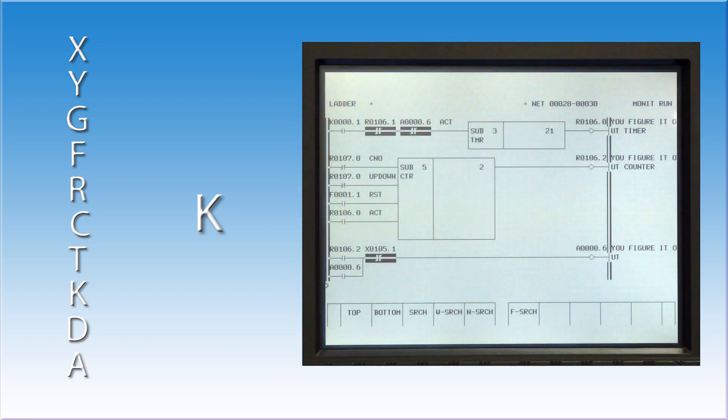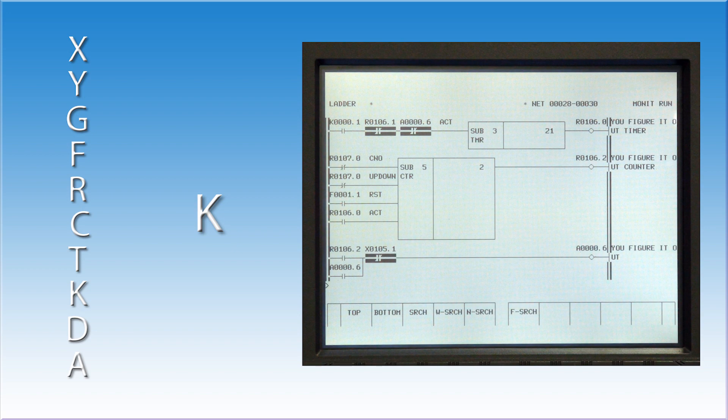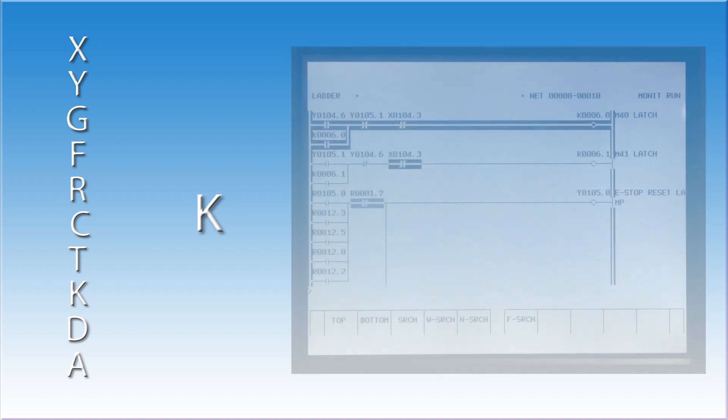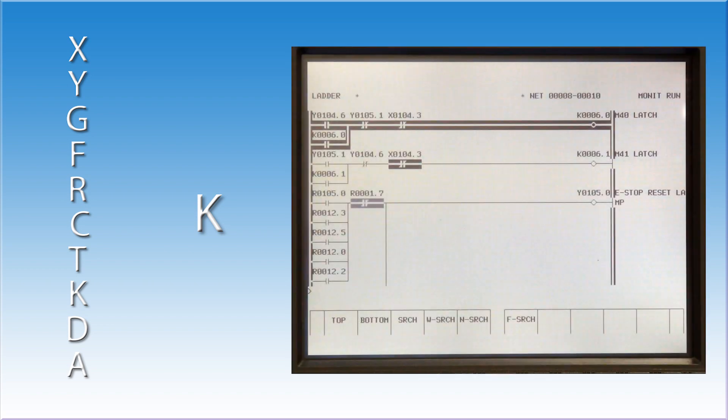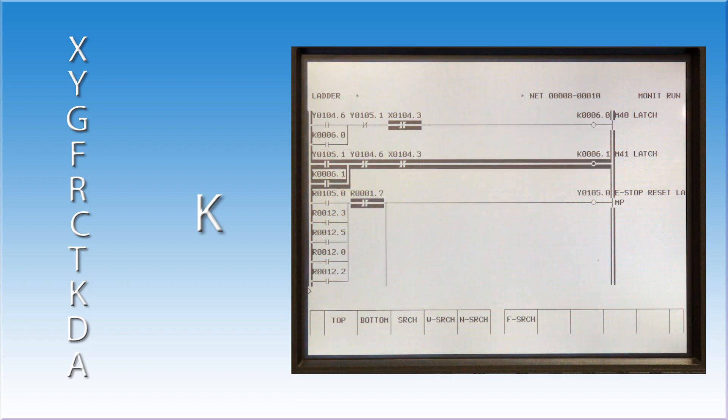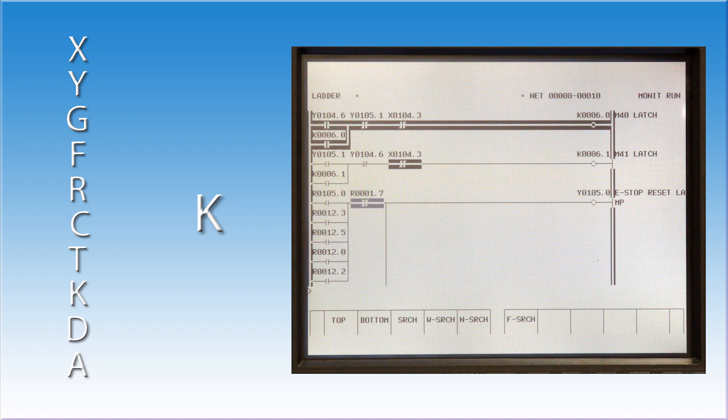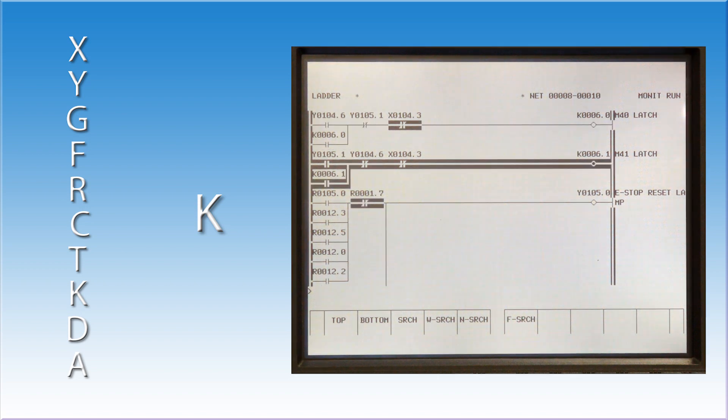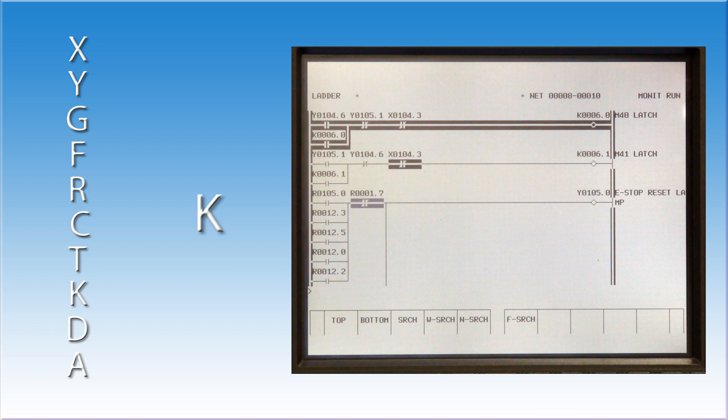The keep relays can also be used to enable or disable certain functions in a ladder logic, such as automatic doors, index tables, or robot interface. Typically, a machine tool builder will write one ladder for a machine model. Not all machines are sold with all options. The machine tool builder will use the keep relays to enable the options that a customer purchased. Keep relays can be used as contacts or coils in the ladder. Some builders use them to retain the status of certain events. Since the last state of the keep relay is retained in memory, it can be used to record information such as what pallet was in the machine when it was shut down, or the clamp unclamp status of a chuck.